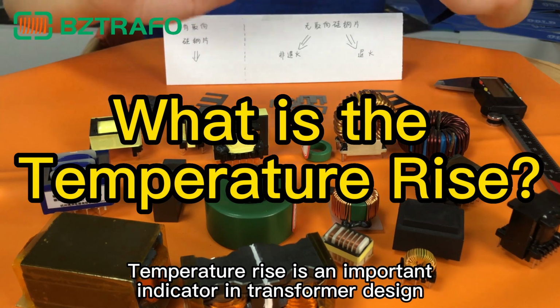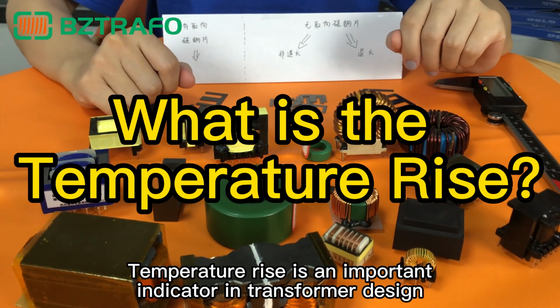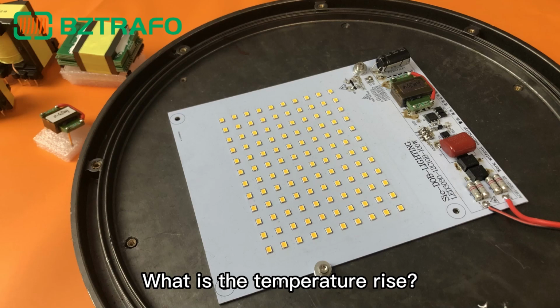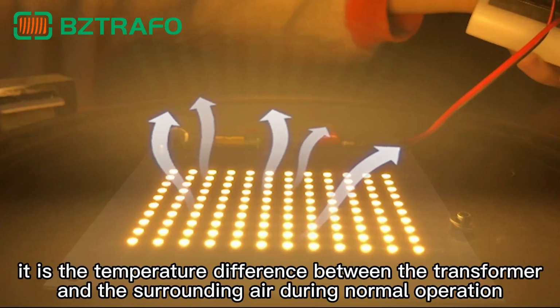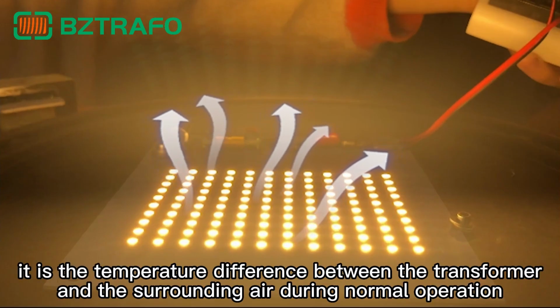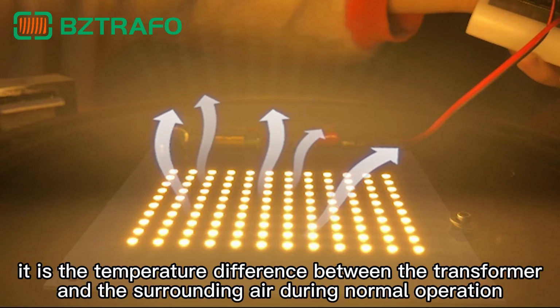Temperature rise is an important indicator in transformer design. What is the temperature rise? Briefly speaking, it is the temperature difference between the transformer and the surrounding air during normal operation.